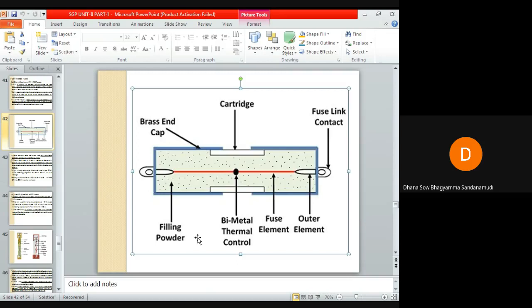Under normal operating condition, the low resistance element will carry the normal current. No current will flow through the high resistance element. When a fault occurs, whenever the current in the circuit is excessive, the low resistance element will immediately blow out, and the high resistance element will reduce the short circuit current. It will try to reduce it, of course, but finally it breaks the circuit.